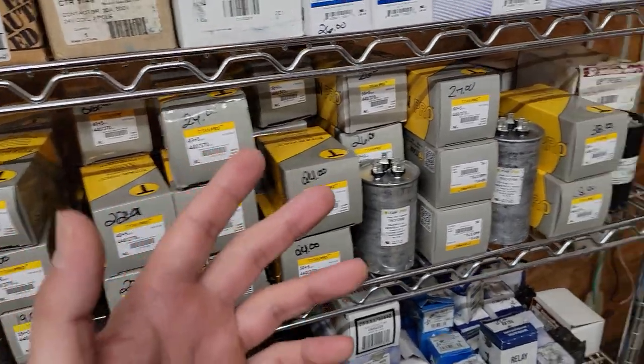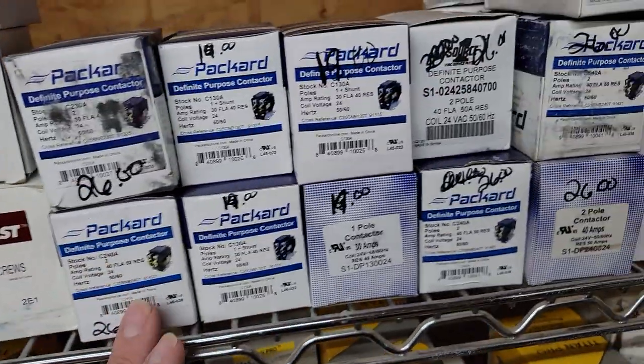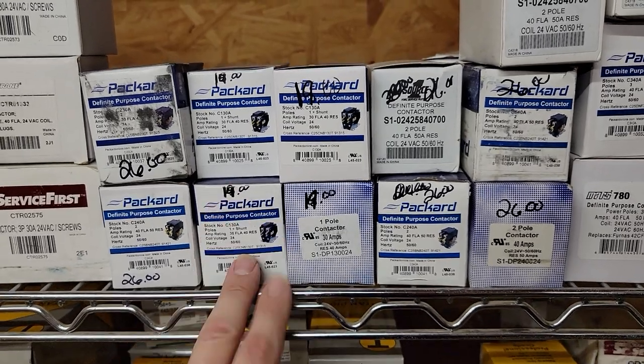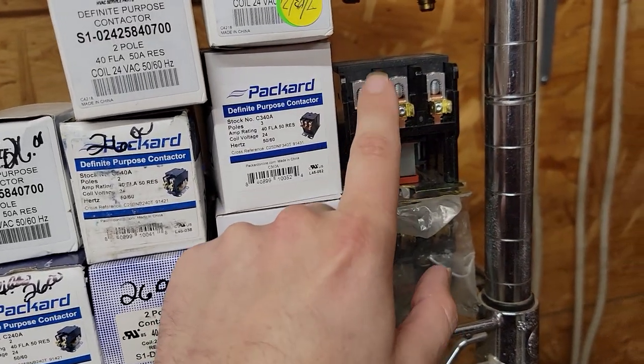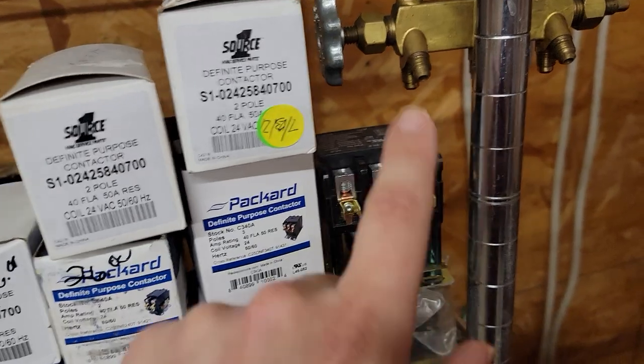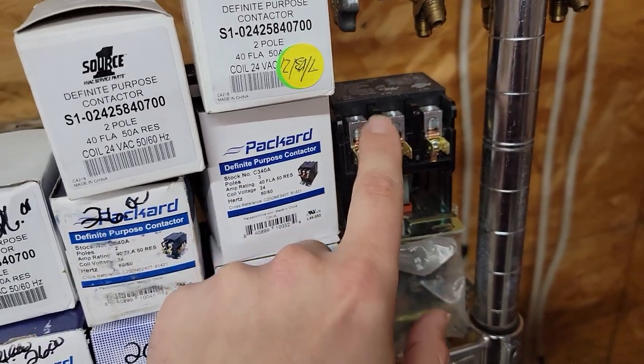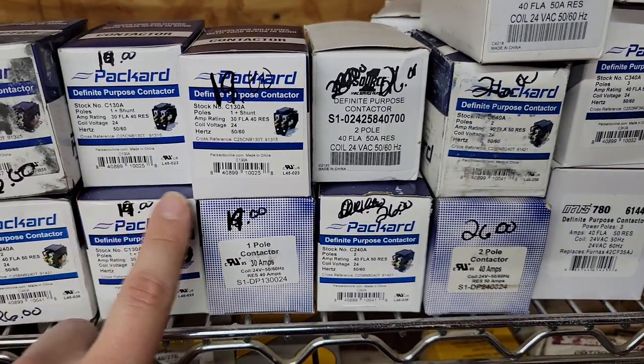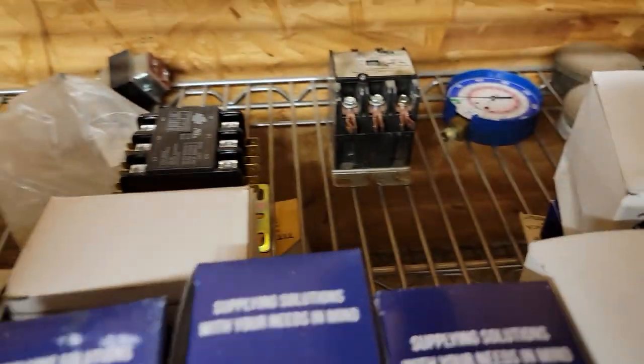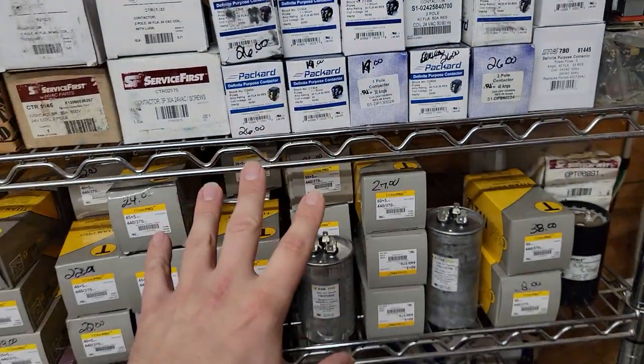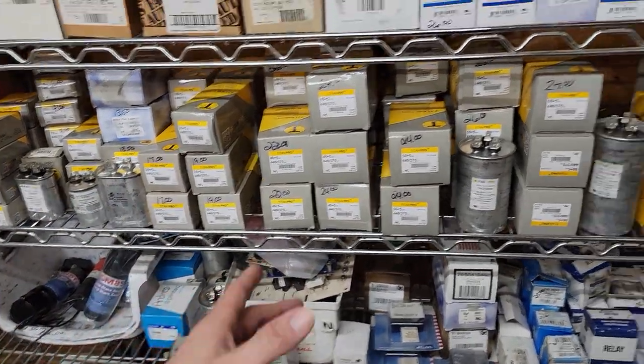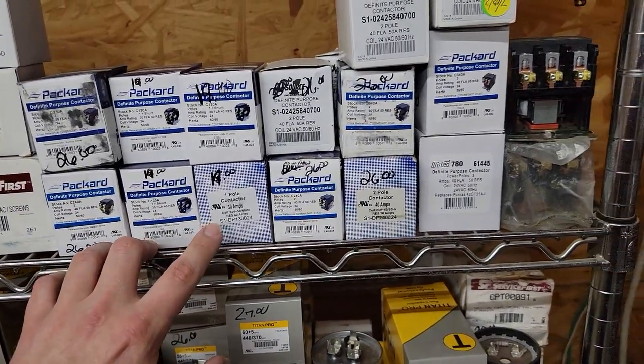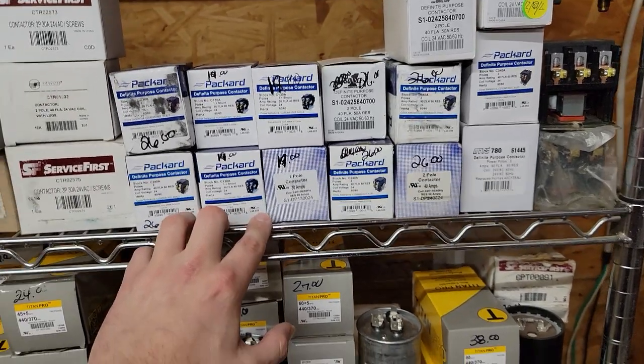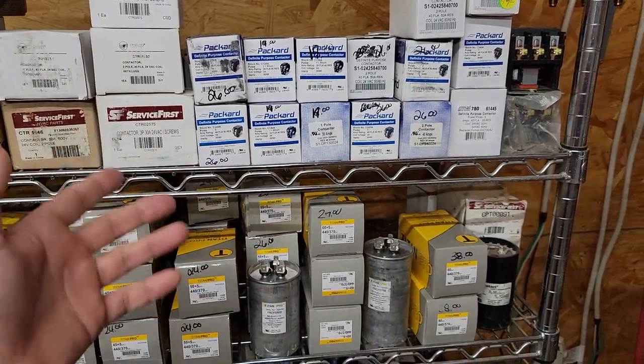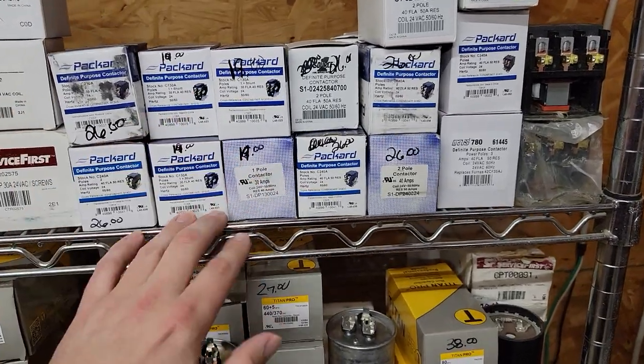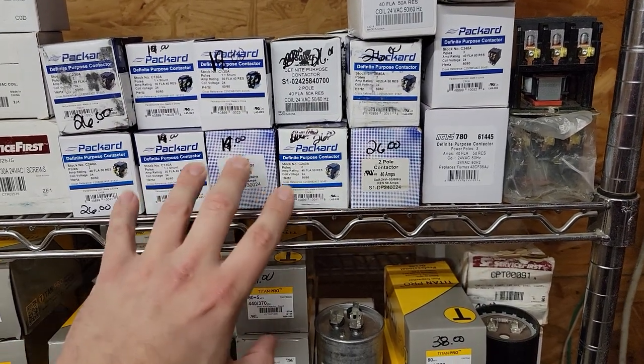And not only do you have these capacitors, but you have these contactors. You have single pole, double pole. We have three pole contactors. This is more your commercial, light commercial and commercial. This is your two pole contactor is more residential. So contactors, capacitors. Why do you have to replace contactor? Well, maybe it's got carbon buildup on the contacts, and it's over time, it builds up carbon and you can no longer clean it because it is just in terrible shape.